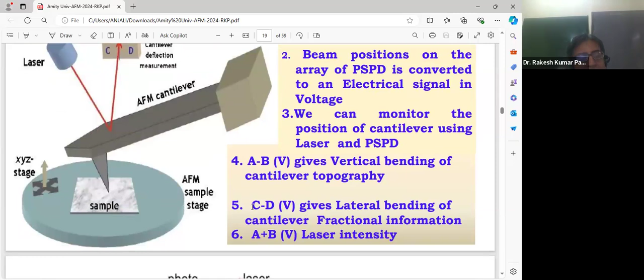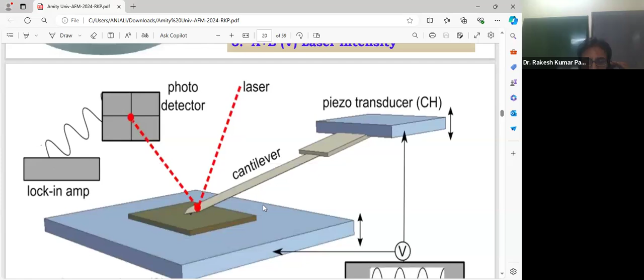We are using an array of detectors, an assembly of detectors. We have combined 4 detectors together: A, B, C, and D. When the light ray falls on the AB detector, it gives the vertical bending of the cantilever, the topography. Detectors A and B are responsible for vertical bending, whereas detectors C and D give the lateral bending of the cantilever. In this way, by observing vertical bending and lateral bending, we can completely scan all the bendings and movements between the cantilever and the sample. The same diagram is shown here.